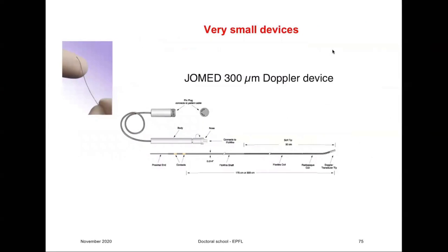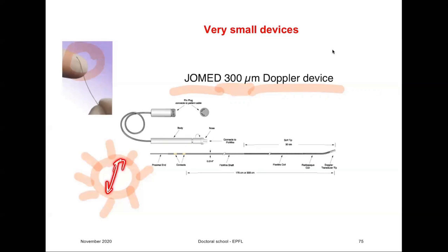So here is a Jomed Doppler device, a catheter, which at its end is just 300 micrometers in diameter, and I think it has 64 piezoelectric elements inside. So imagine putting 64 elements on 300 microns. They are distributed around the perimeter of this 300 micron diameter, and then you can look in all directions when this enters your blood vessels, and it can go all the way to the heart to see what's happening there.